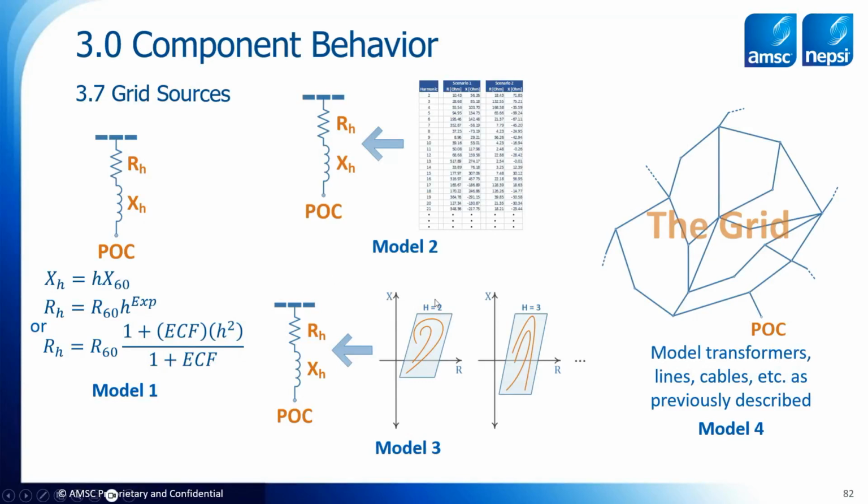And so what they'll do is at each harmonic, they will supply you a polygon. And within that polygon, when you do your analysis at the second harmonic, you can expect it to be any number within this polygon. And for the third, it's a different shaped polygon, and it will have any number within this polygon. Now, how you select and where you pull from out of these polygons to do your analysis is a whole interesting conversation that we could have.